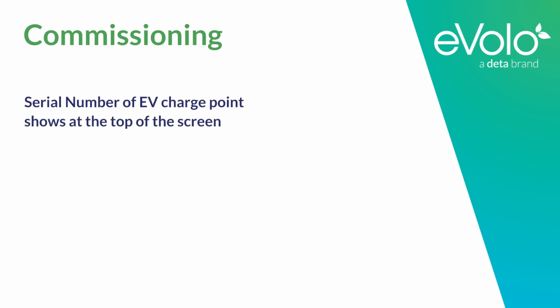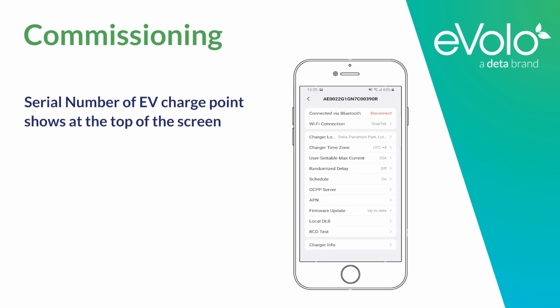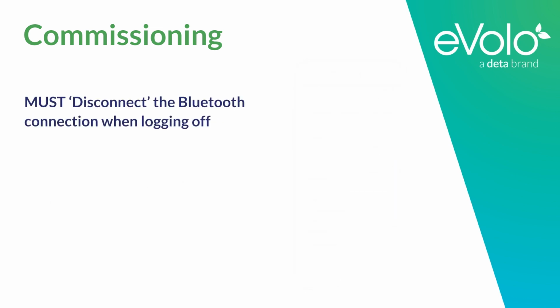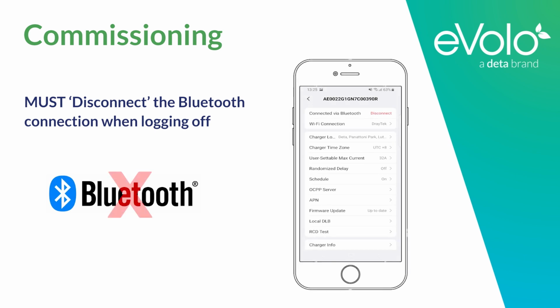After that, work through the fields within the setup screen, entering charger location, time zone and so on. The maximum current that the user can charge at is set in this field, which may be particularly important if the DNO fuse is lower than 100 amps and there are other heavy loads on the installation. Setting primary and secondary charge points maximum supplies available is also done in the local DLB field. When you are finished, make sure you disconnect your Bluetooth connection, otherwise the end users may not be able to connect.